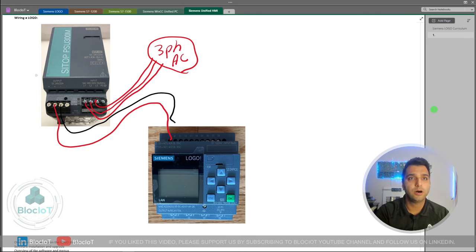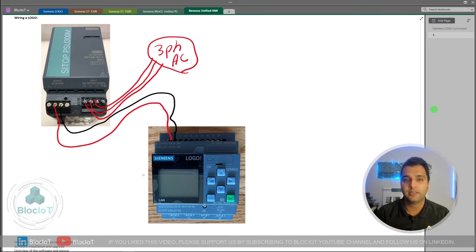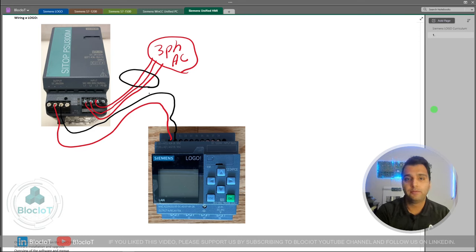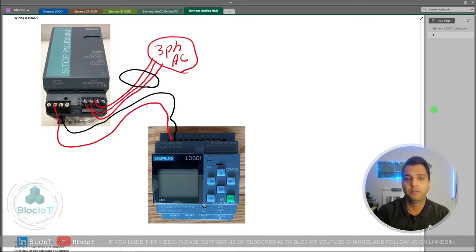As a best practice, it is suggested to use fuses to control the maximum current between every connection. We will definitely need fuses or breakers in the main power supply. Bear in mind there are two different types of fuses — AC and DC — so on the inputs you will need AC fuses, and on the output you will need DC fuses if you want to fuse your power supply-to-Logo connection.